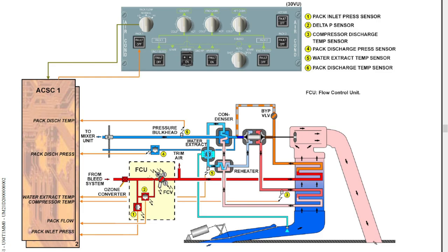And I told you that the flow control valve has two modes, normal mode and pneumatic backup mode. That part is controlled by the other solenoid, and it also has two states, energized and de-energized. If that normal and pneumatic backup solenoid is in the energized state, the flow control valve will operate in normal mode. If it is in the de-energized state, the flow control valve will open in pneumatic backup mode. So that is a different story, right?